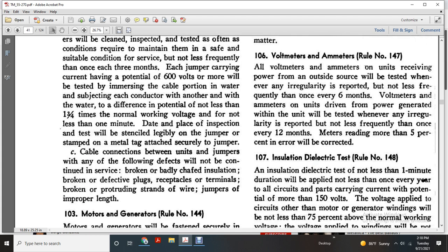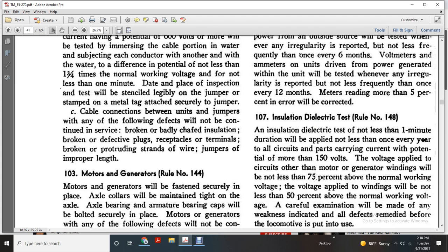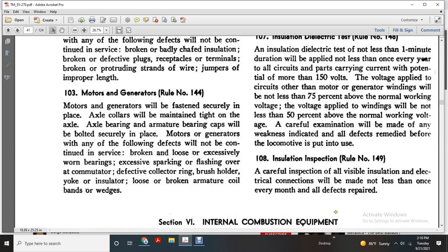107, insulation dielectric test, rule number 148. An insulation dielectric test of not less than 1 minute duration will be applied not less than once every year to all circuit parts carrying current with a potential of more than 150 volts. The voltage applied to a circuit other than motor generator windings will be not less than 75% above the normal working voltage. The voltage applied to the windings will not be less than 50% above the normal working voltage, and careful examination will be made. Any weakness or indication of defects will be remedied before locomotives are put into use.